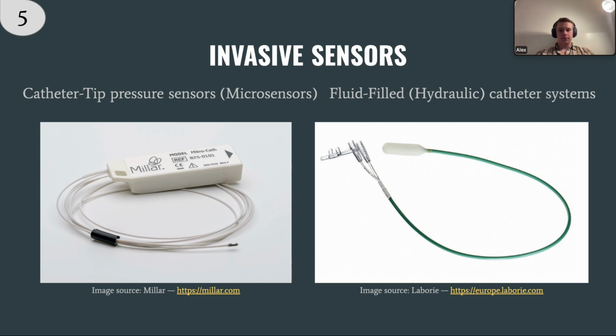These are invasive sensors, and they are very accurate because the sensors are very close to the artery. And the second type is called fluid-filled hydraulic catheter systems. These devices are basically filled with salt water. The blood flow pushes the water to the sensor, then the sensor turns it into an electrical signal and gives it to the machine. The same idea.